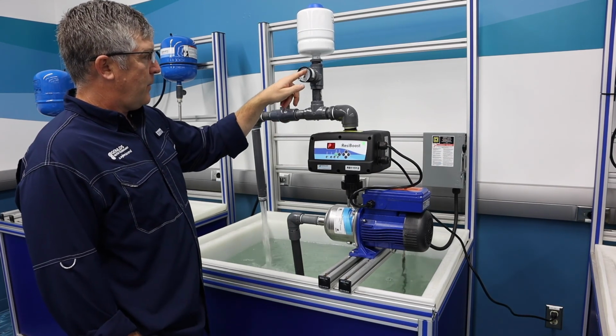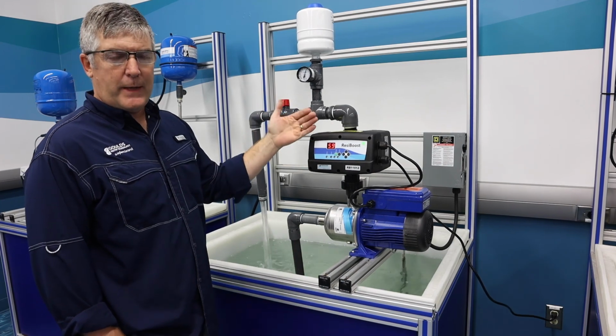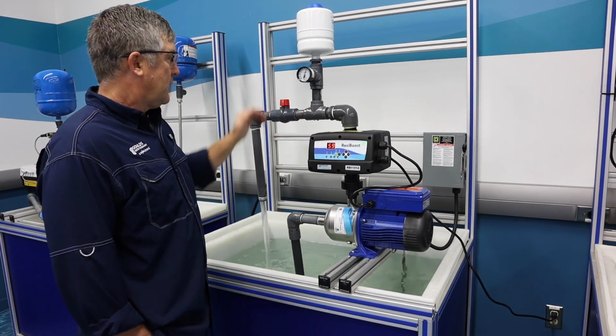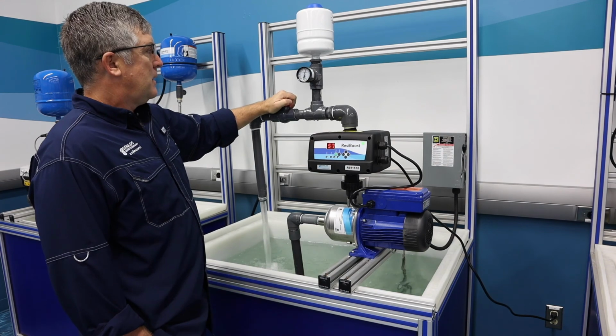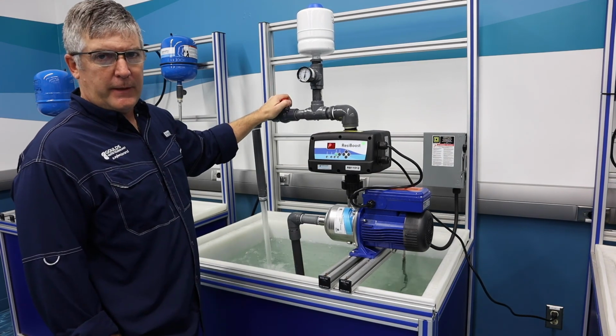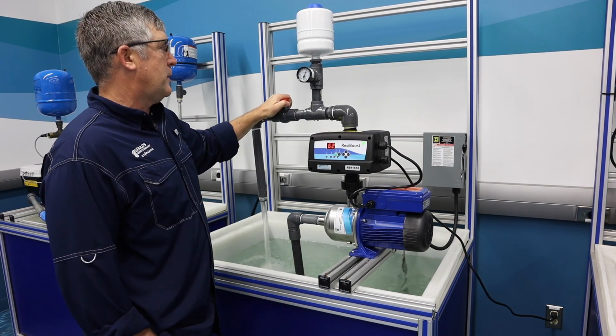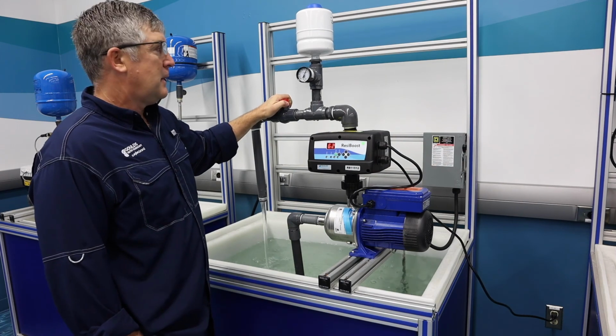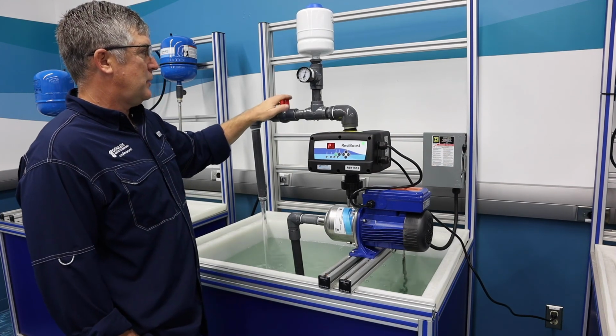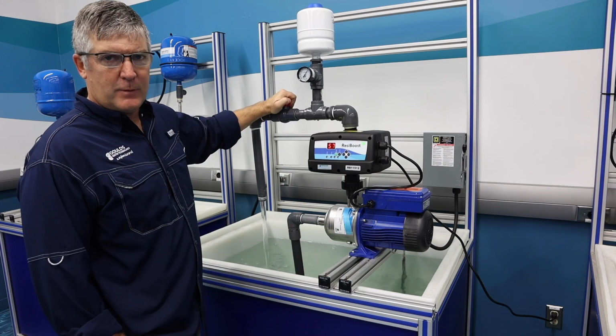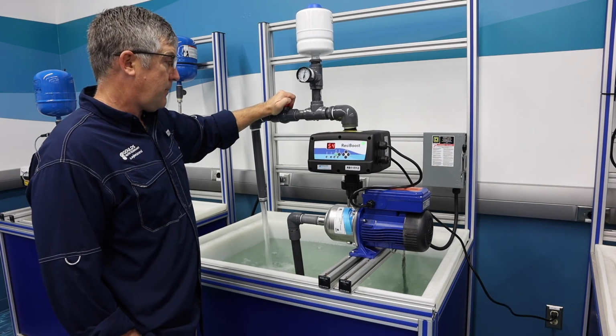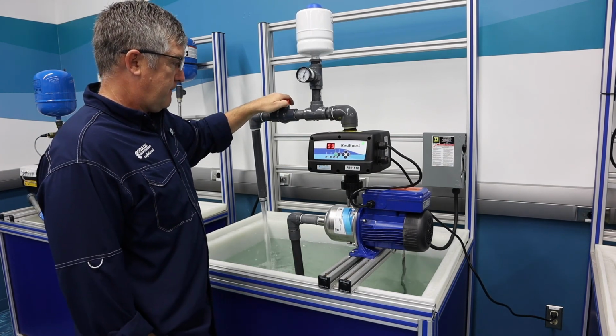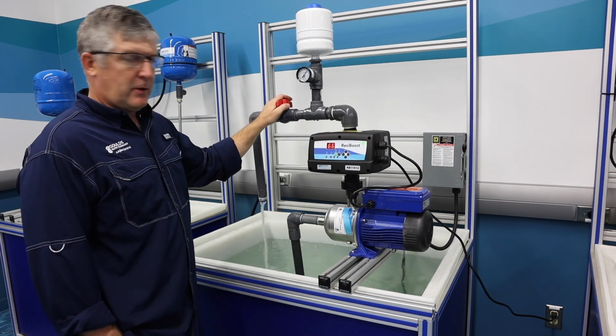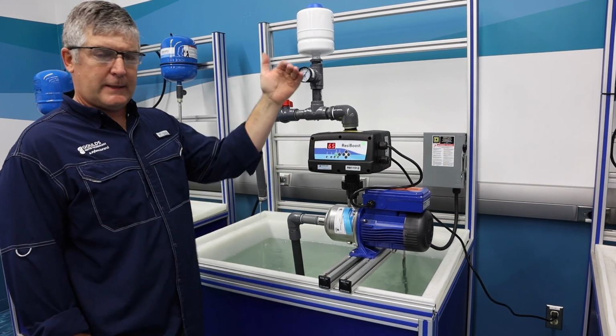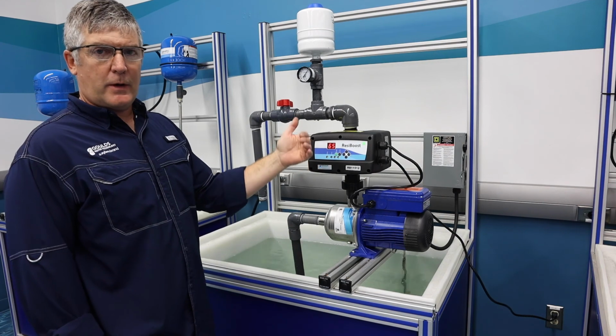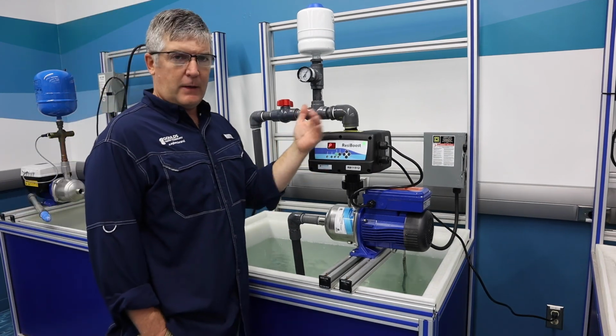And we want to maintain, like in our case here, 60 psi constant pressure, regardless of the demand. So whether I open it or close it, it is going to try to maintain that 60 psi. And if I close the valve, it's going to get down to the min frequency, which in our case is 30 hertz, and then it's going to turn off.